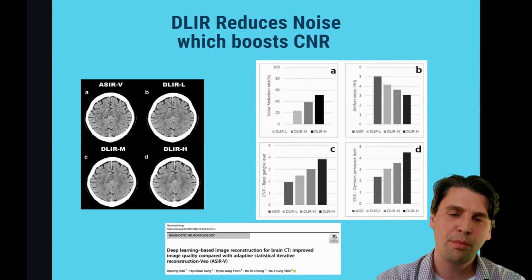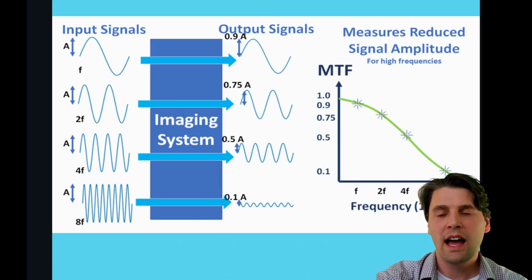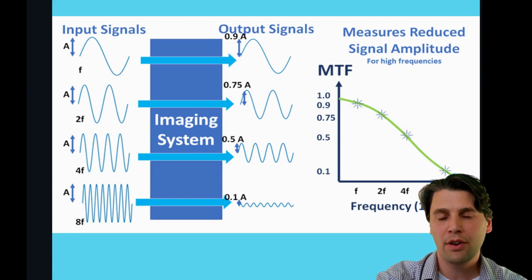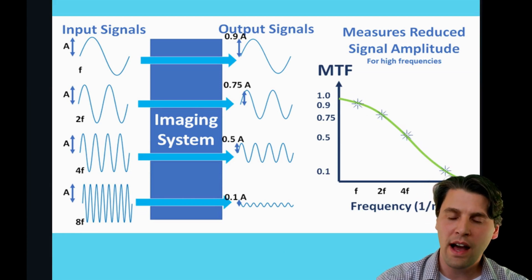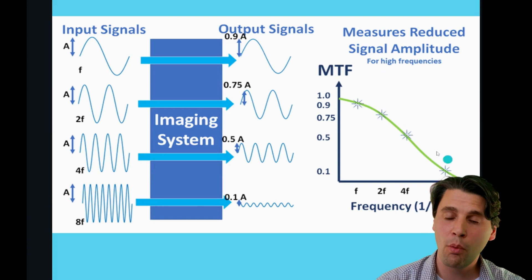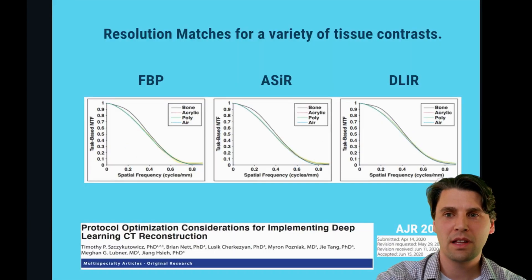The clinical modulation transfer function (MTF) looks at how different frequencies will propagate through the imaging system. In general, the higher frequencies — values that change more quickly — will be attenuated more as they go through the system. So your MTF will typically look something like this, showing that attenuation as a function of spatial frequency.